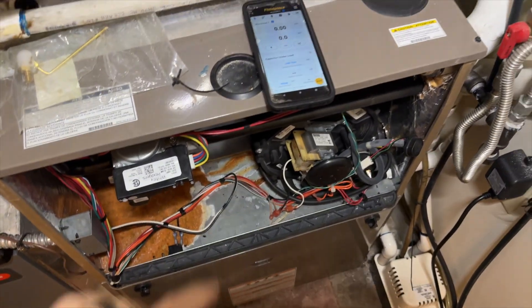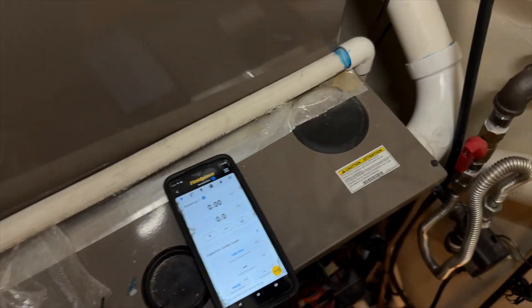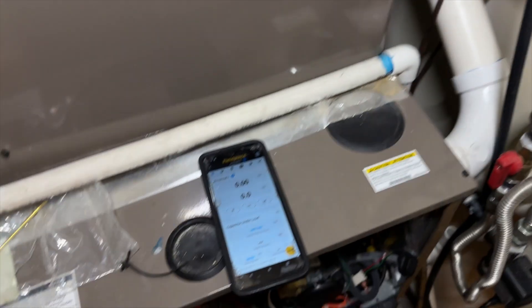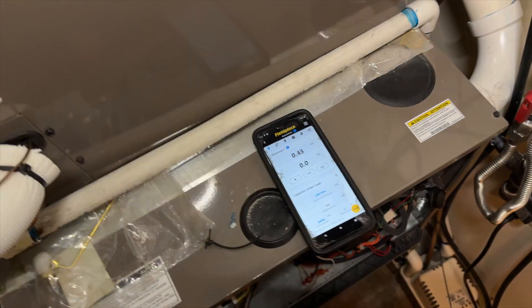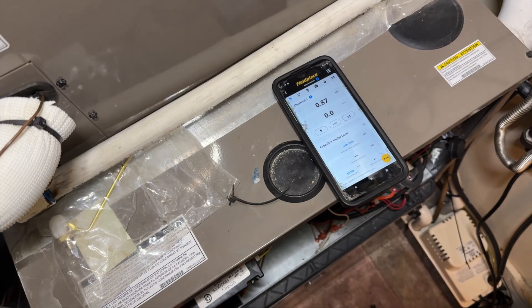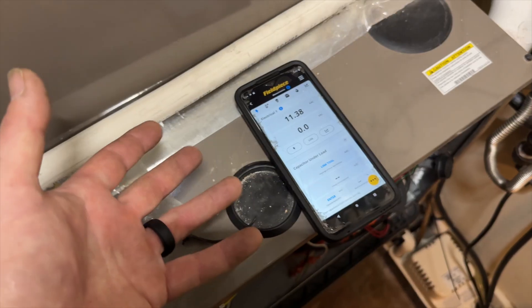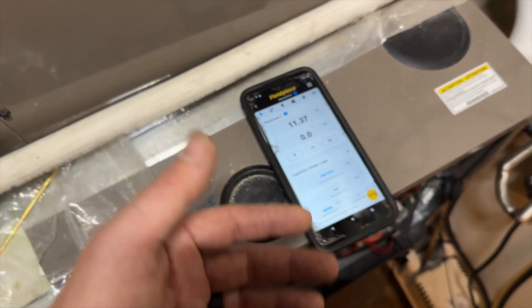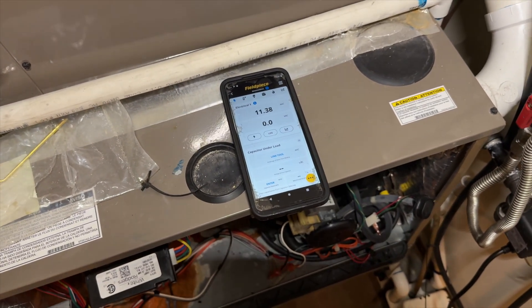I put the door back on just to act like it would normally. We're connected to the meter wirelessly. I'm going to put it in cool mode to get the thing to run full blast. In fan mode calling for G, we were getting about 12 amps. With the door off we're pulling in more air, actually decreasing the static pressure — more volume puts a higher load on it. So that's why it reads a little bit lower with the door off.